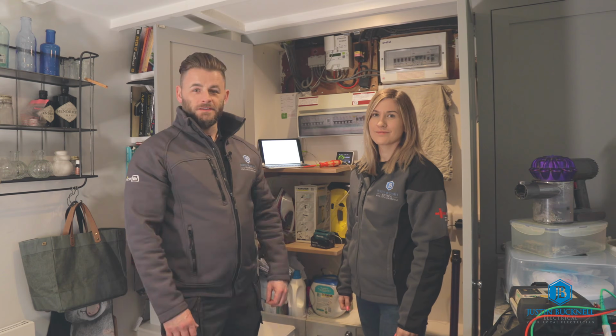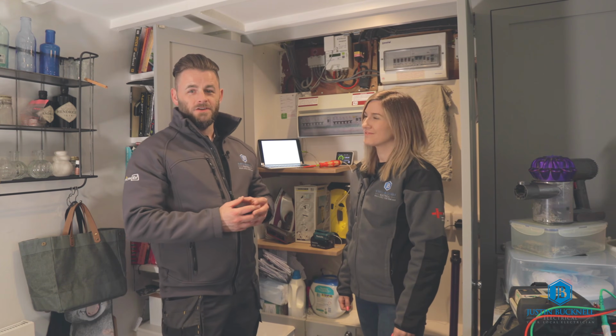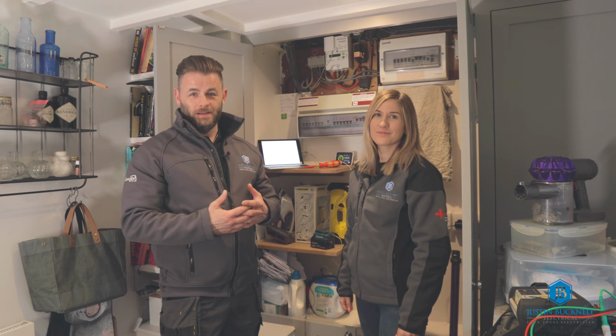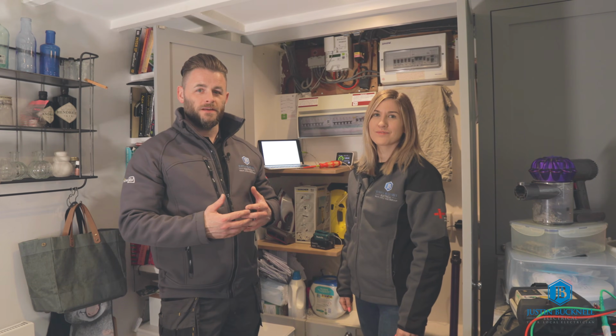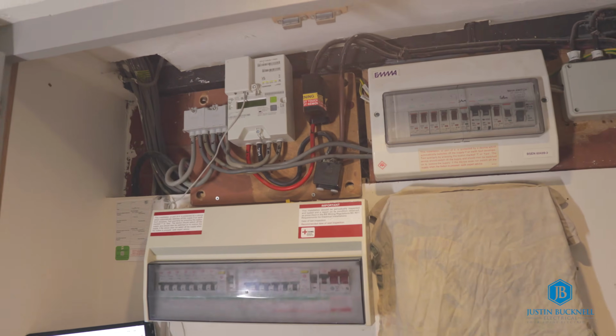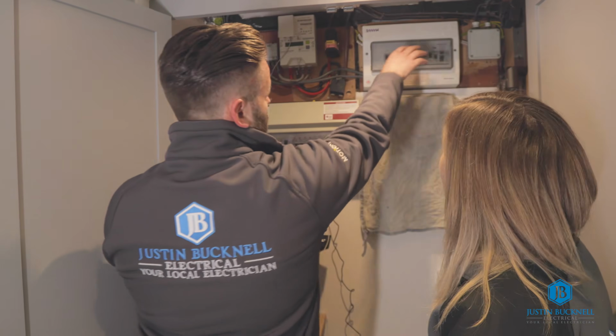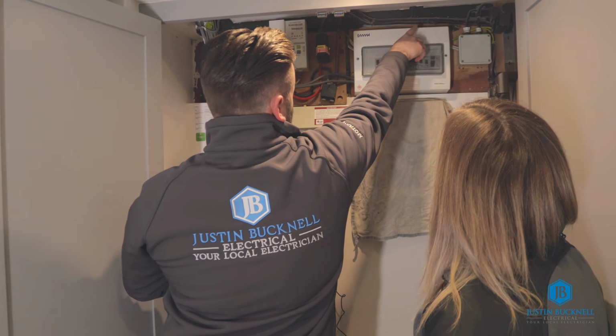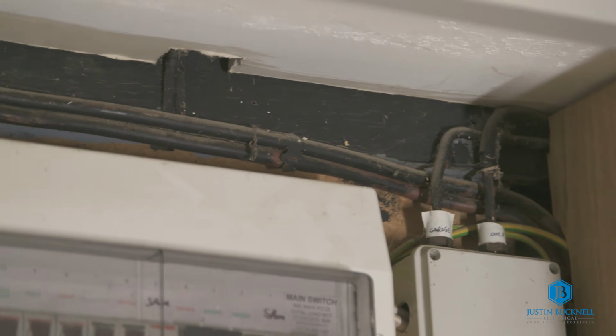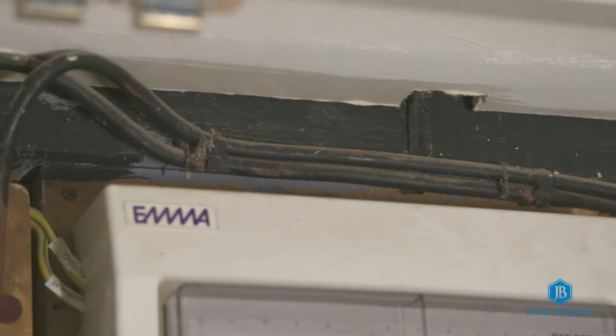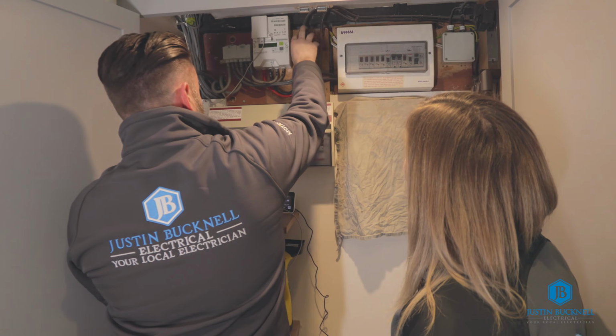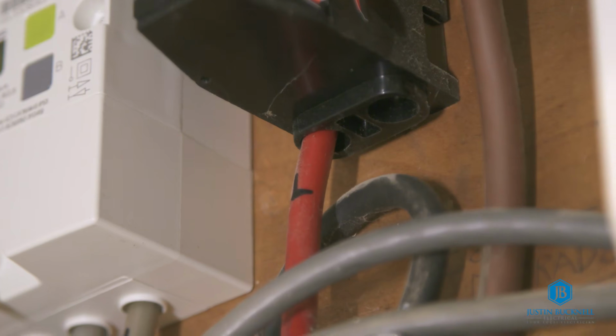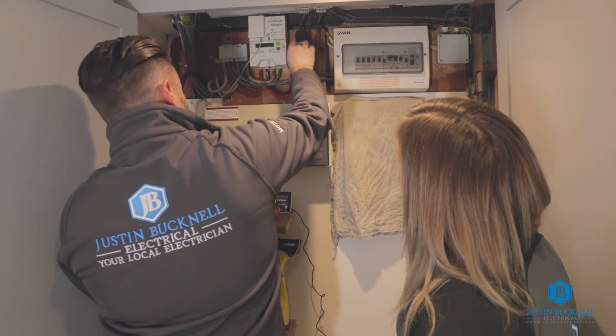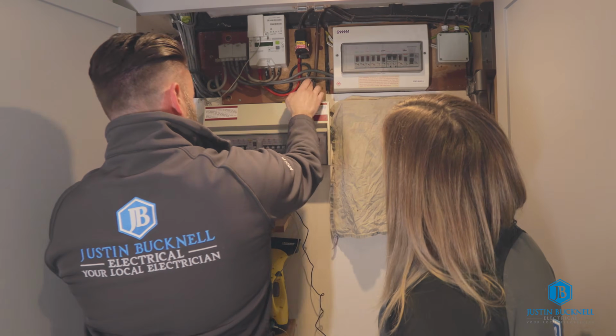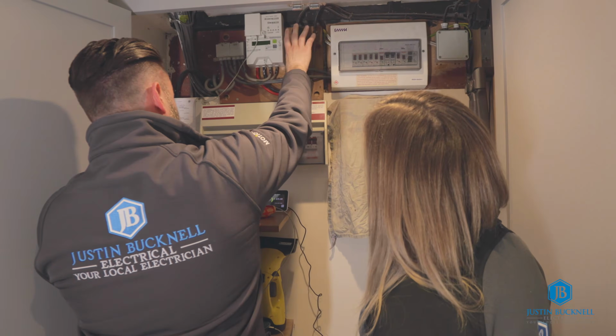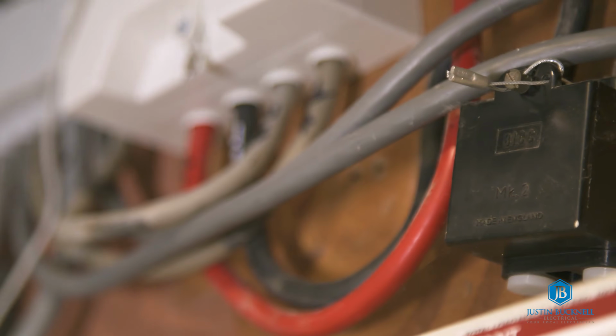So we're joined today by Gemma from the office. She's come along with us to also gain a better understanding of what is involved in an electrical installation condition report. So these cables that come across the top of this consumer unit here, these are actually the supply cables coming in. So this one that goes into this item here, this is the main fuse. So this is the main DNO live cable coming in. And then this one here is the neutral, and this goes into a neutral terminal here. Okay. This then passes through to the meter.